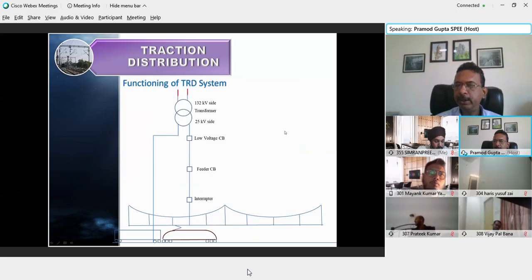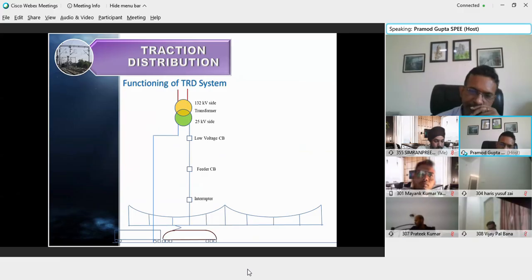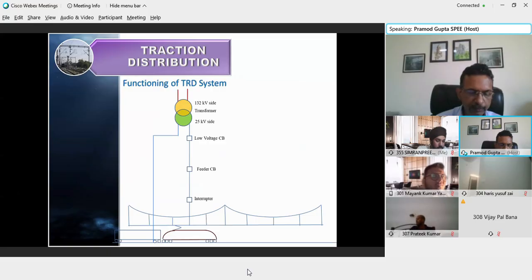Let us see the overall functioning of the TRD system. We get the power supply at 66 kV and above. After stepping down using the power transformer, the output voltage is 25 kV. Then we have the first circuit breaker, the low voltage circuit breaker. Its function is to sense the incoming voltage level. If the incoming voltage is found to be very low, the circuit breaker will not close and no power supply will be extended to the OHE system.